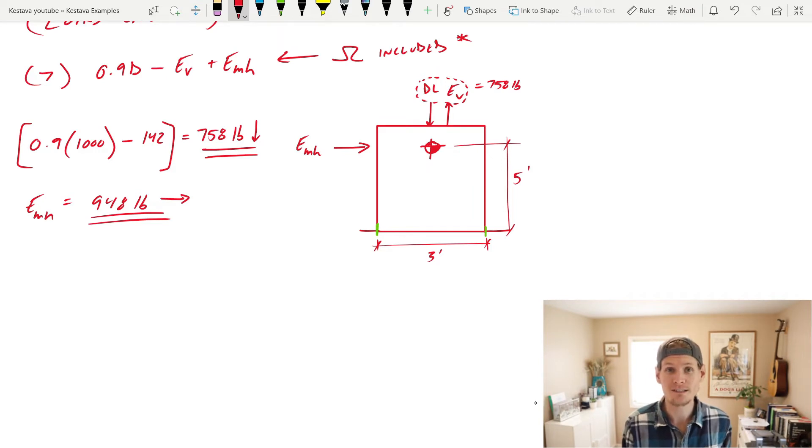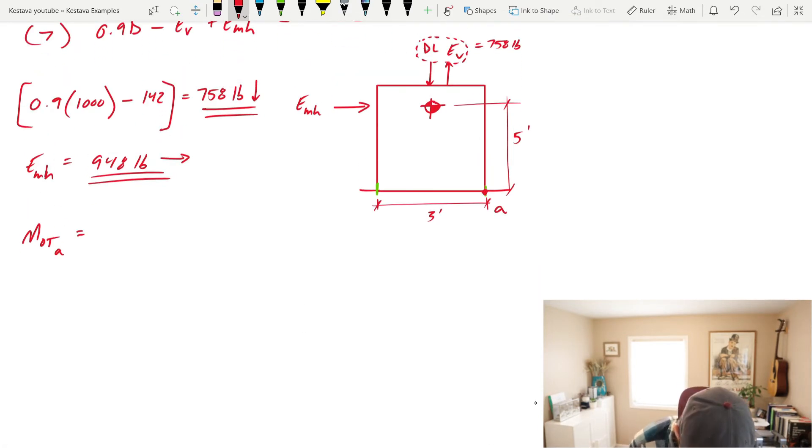Let's now transform these loads into loads that are going to be experienced by each one of the anchor points. For that, we need to first find overturning. And let's take it about point A. I'm going to go right there. Your overturning is just EMH times five feet. And for those not following along, EMH is applied to your center of mass of your unit. And this, that is our datum that we give here. I'm going to say center mass CM. That is almost always given by your unit manufacturer. So you're given a unit and you're given a cut sheet that says all these different components and dimensions and weights and all of that stuff is within that cut sheet by the manufacturer that made that unit. And with that, they also give you a center of mass that you then use for your calculations like we're doing right now.